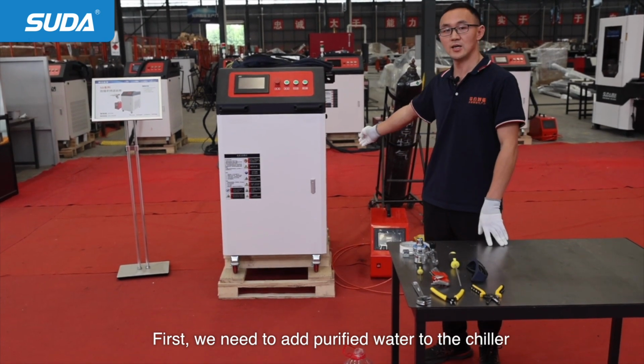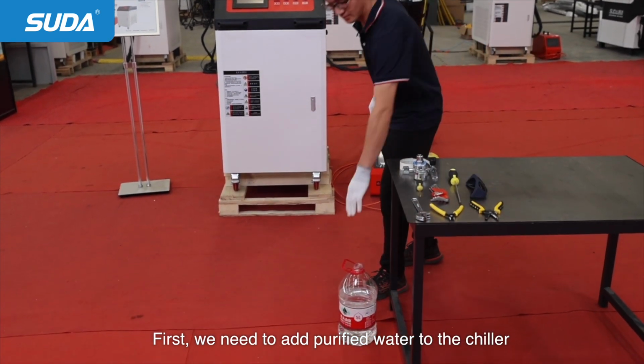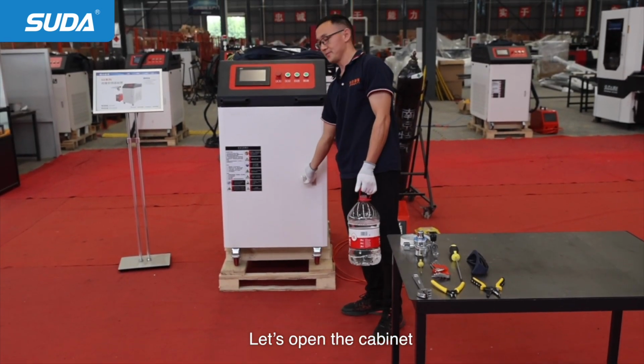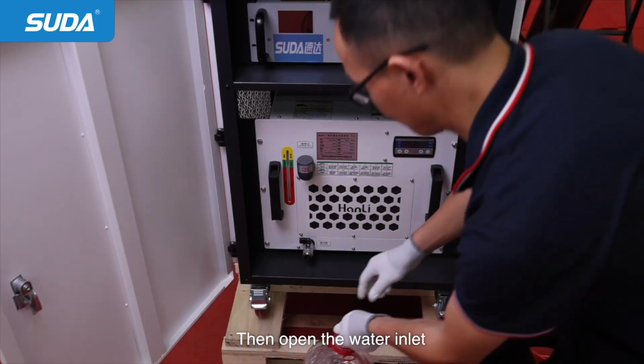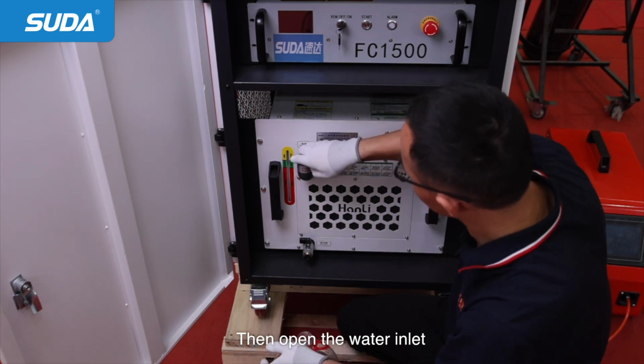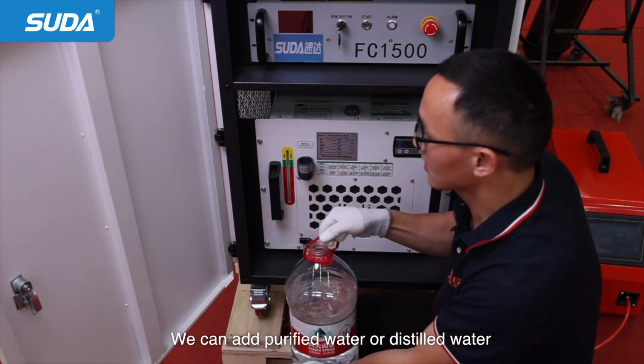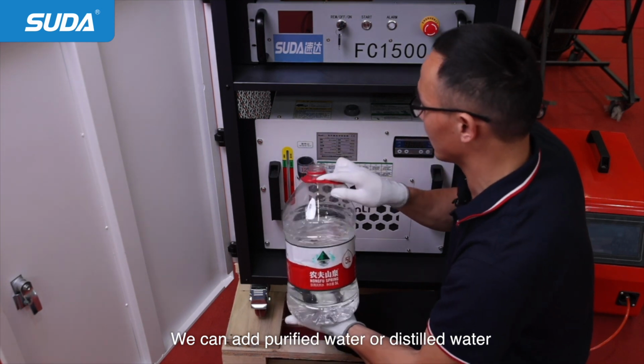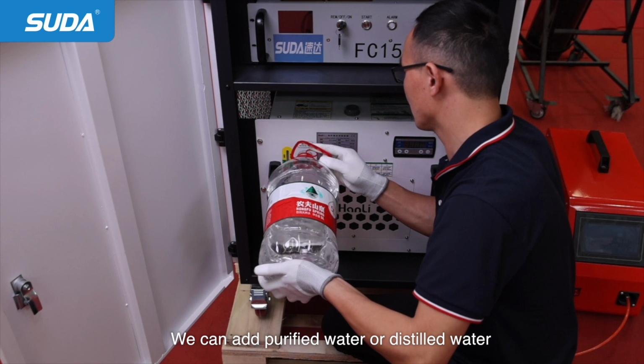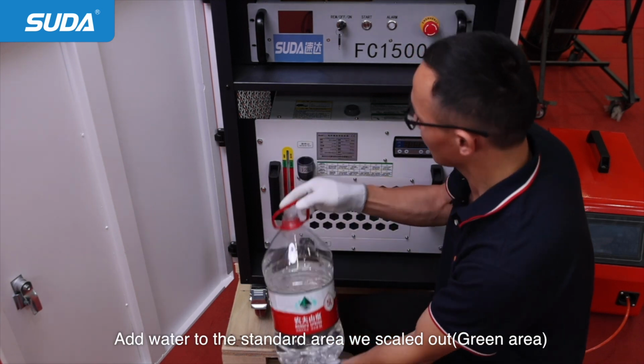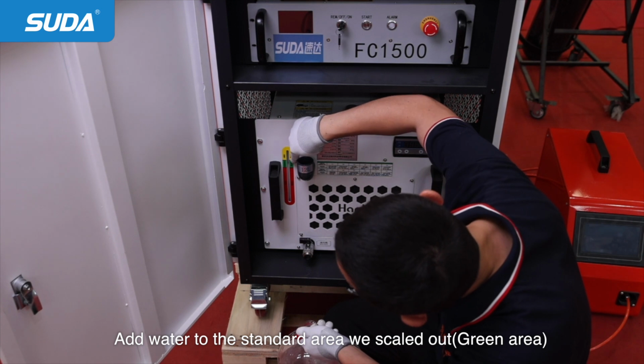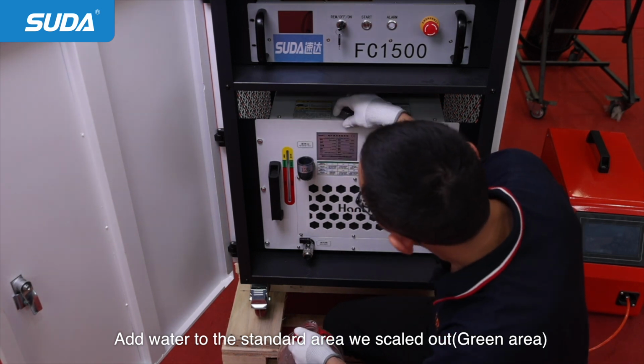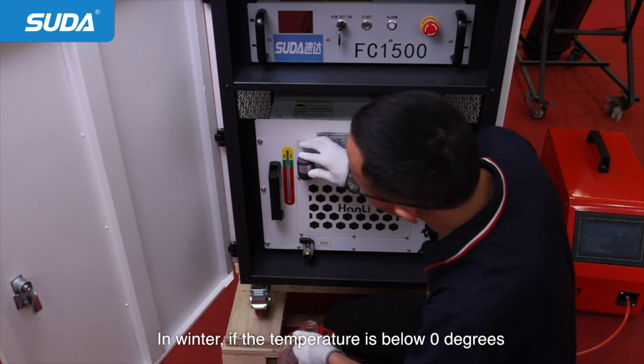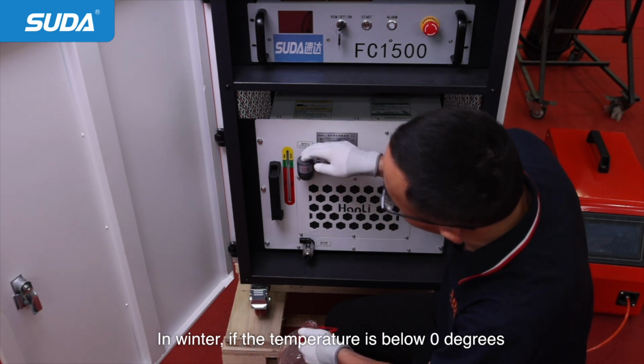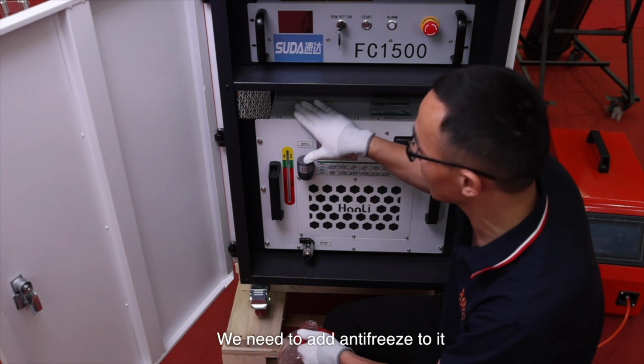First, we need to add purified water to the chiller. Let's open the cabinet. Then, open the water inlet. We can add purified water or distilled water. Add water to the standard area we scaled out. That means the green area. In winter, if the temperature is below 0 centigrade, we need to add antifreeze in the water.